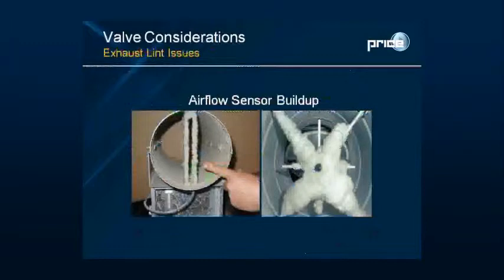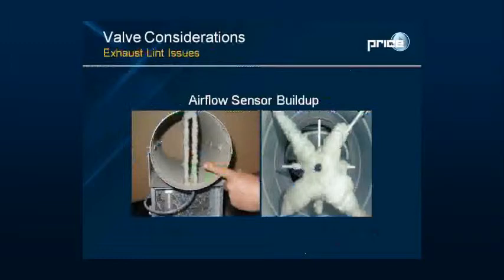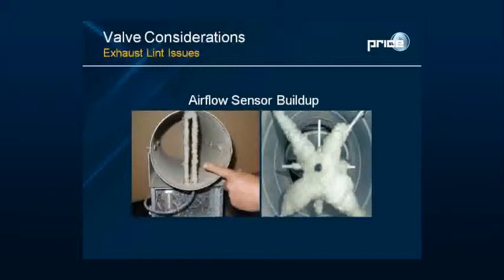Another issue with conventional VAV boxes is potential buildup on cross-flow sensors. In return or exhaust applications such as isolation rooms and operating rooms, there is a high concentration of airborne lint from frequent linen changes. This lint can accumulate on cross-flow sensors and interfere with the velocity pressure signal. The Venturi valve avoids this issue entirely because it does not use an airflow sensor to control flow.